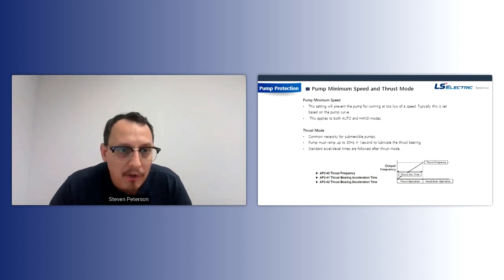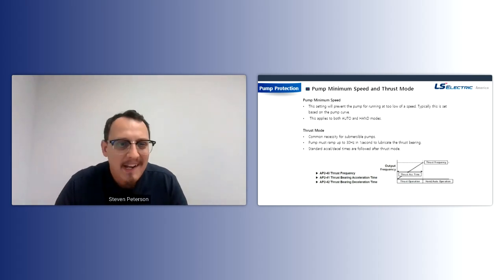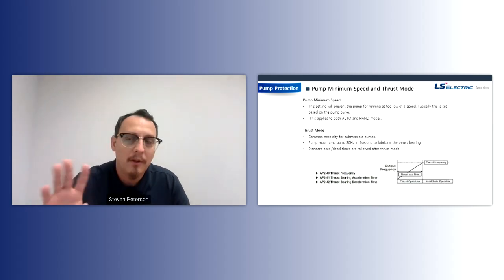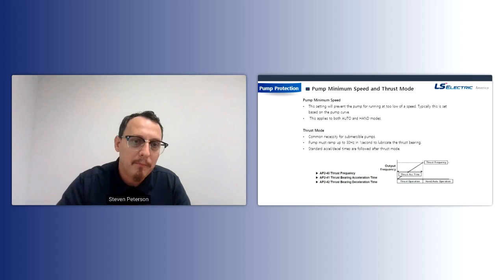A couple more here. First is minimum pump speed. Pumps really don't do much work. They're not building up much pressure when you're running them at a low speed. So a lot of times we set up a minimum pump speed, 30 hertz, 40 hertz, depending on what type of pump you have. That means even if you're telling the drive to go to super low speed, it's going to say, no, I'm not going to listen because you told me I have a minimum speed.